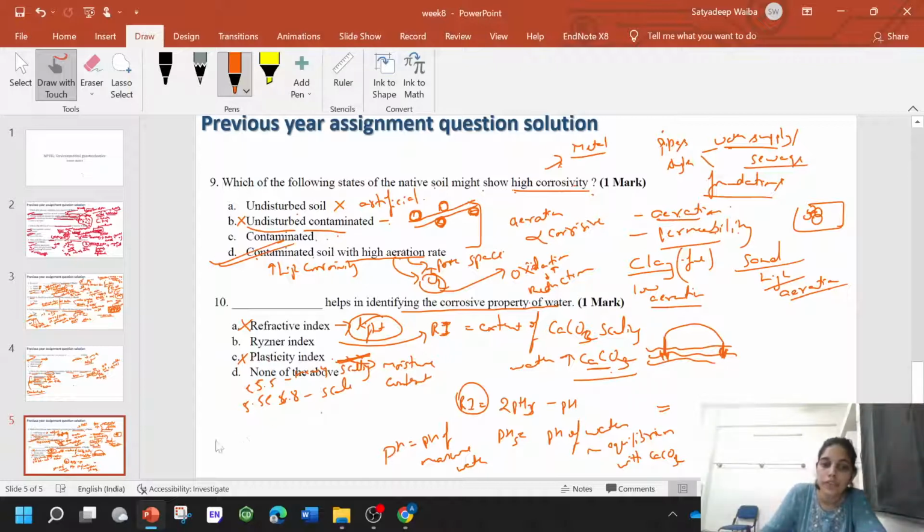If your Ri goes above 6.8 or above 8.5, it becomes corrosive. As long as the Ryznar index of the water is less than 6.8, there will be scaling of CaCO3, but it will not corrode the system or the foundation.